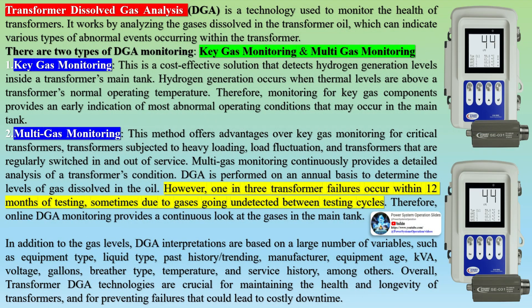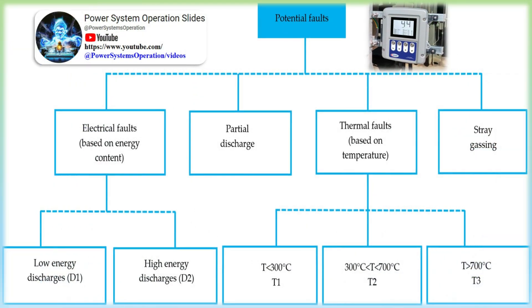Key gas monitoring is a cost-effective solution that detects hydrogen generation levels inside a transformer's main tank. Hydrogen generation occurs when thermal levels are above a transformer's normal operating temperature. Therefore, monitoring for key gas components provides an early indication of most abnormal operating conditions that may occur in the main tank.